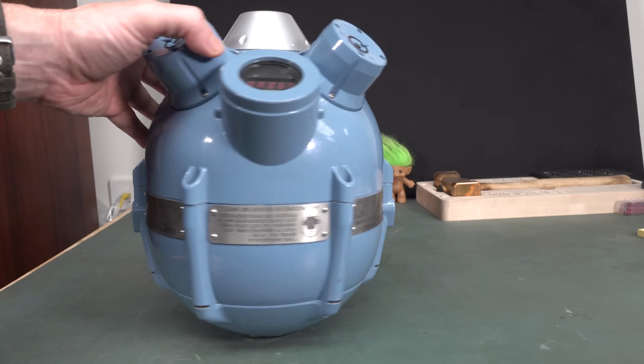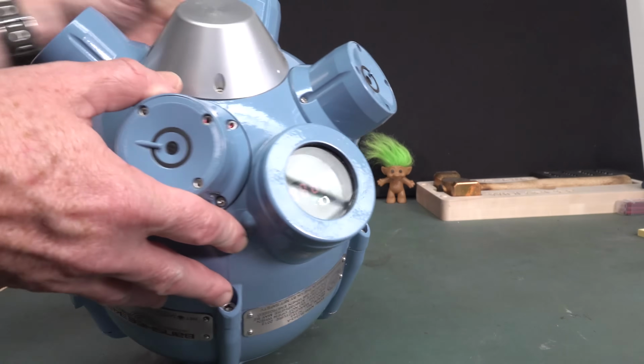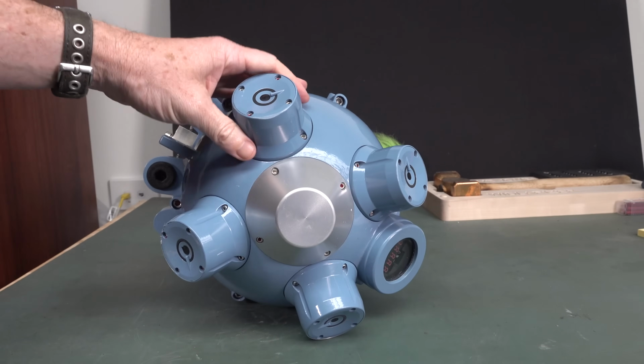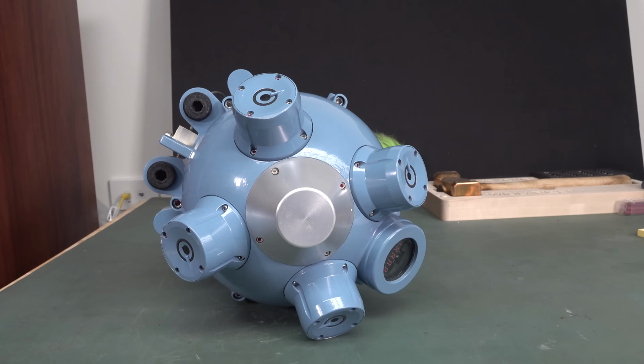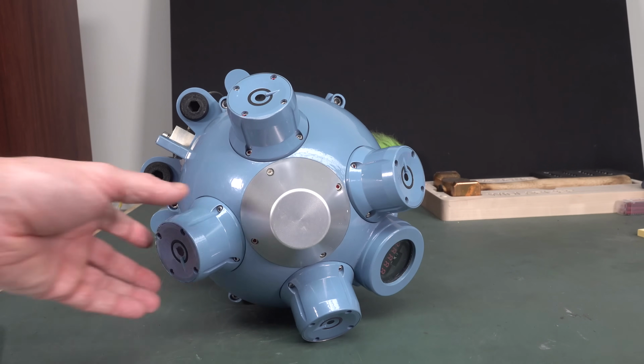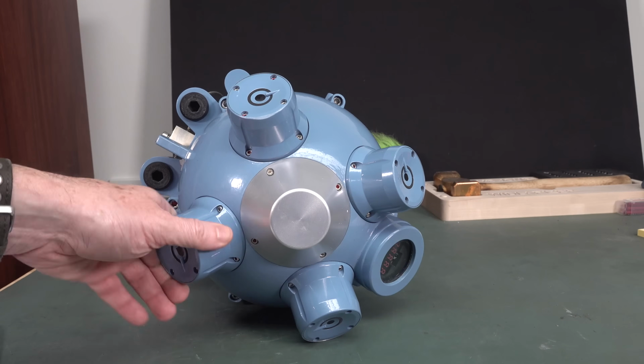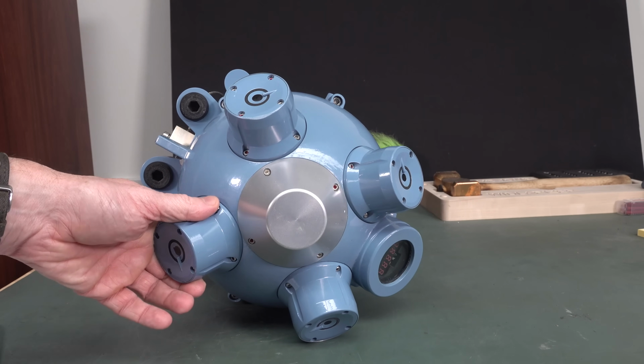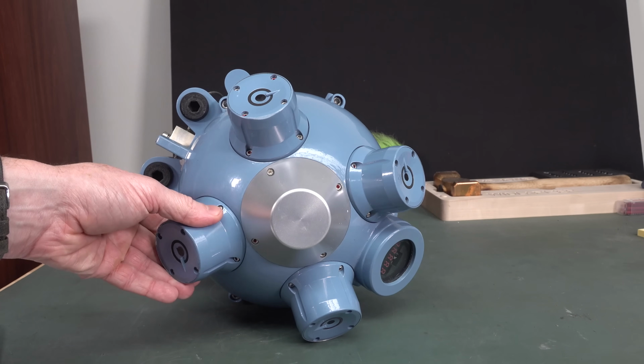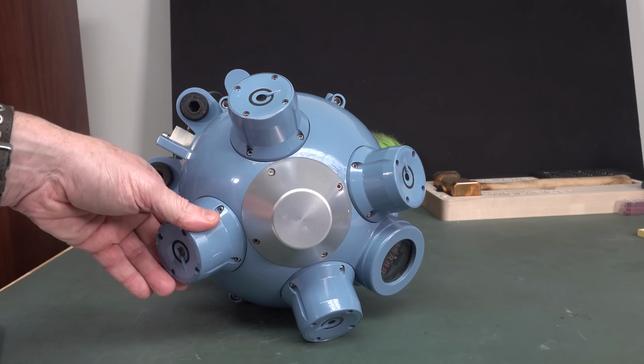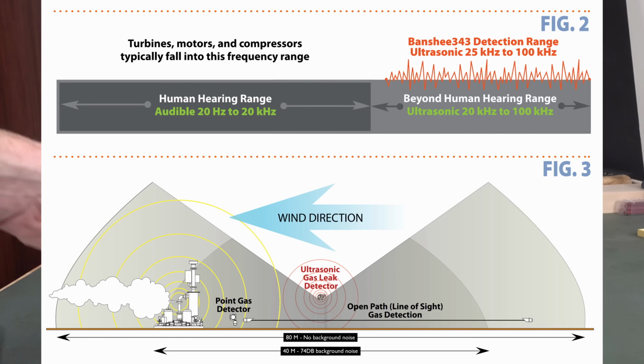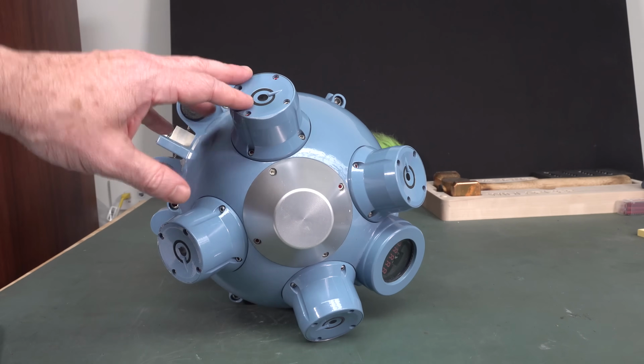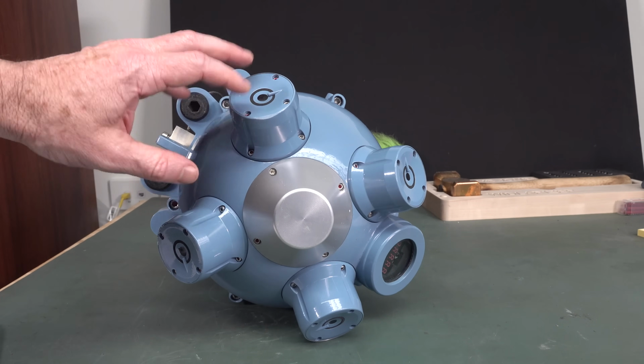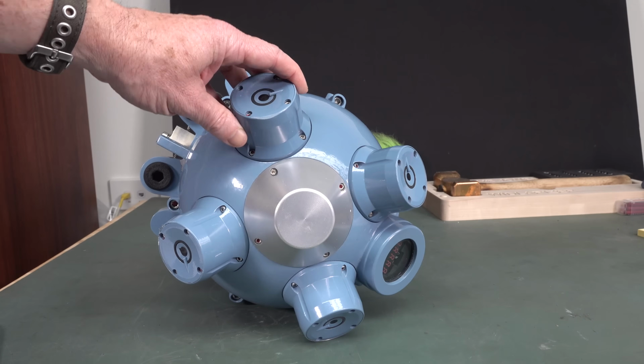So who knew that when pipes leak, they generate not only audible hissing sounds but ultrasonic sound as well. This is designed to measure a 40 meter radius and works from 25 kilohertz to 100 kilohertz, and can work from anywhere between 50 dB to 160 dB pressure levels.